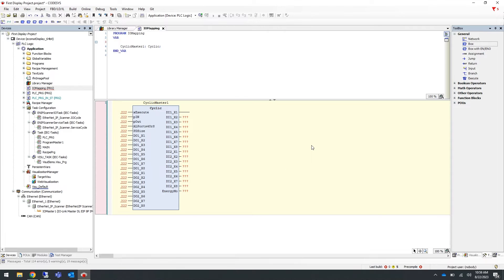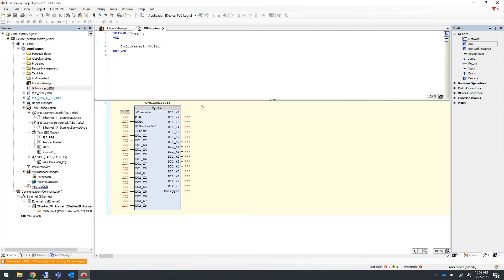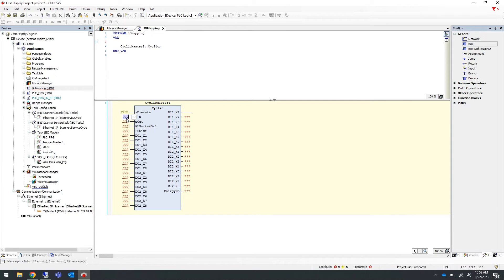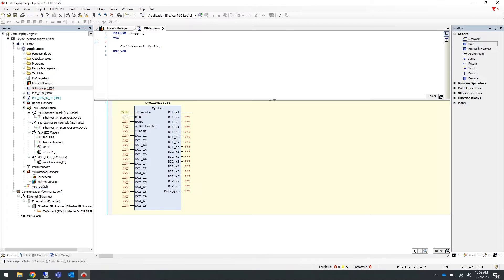Now let's configure this function block. First, set the x execute boolean to true by double clicking on the question marks and typing true and pressing enter. Next we have to set the input and output variables to the variable names for the starting points of the input and output array. We will do this using the ADR syntax, so type ADR, open parenthesis, the name of your starting point of your input array which was input master one, then end parenthesis and press enter. Do the same for the output array.